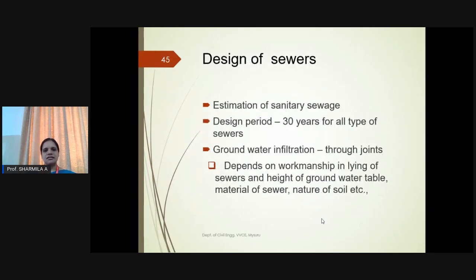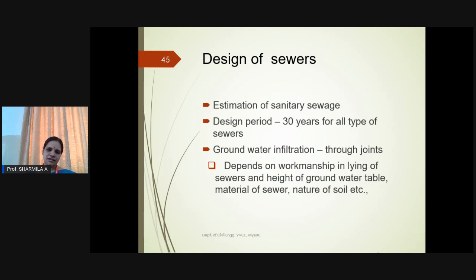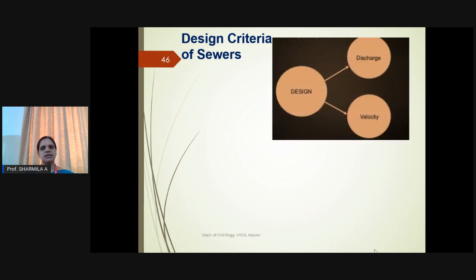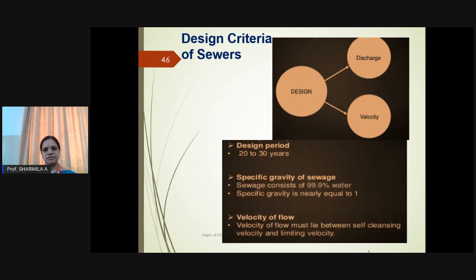Maximum and minimum rates of sewage flow are controlling factors in the design of sewers. Sewers must have ample capacity to carry maximum flow and also ensure sufficient velocity for self-cleansing at minimum flow. For design of sewers, the design period is 30 years, and groundwater infiltration through joints is also considered. The specific gravity of sewage is nearly equal to 1 since it is 99.9% water. The velocity of flow should lie between self-cleaning velocity and limiting velocity.